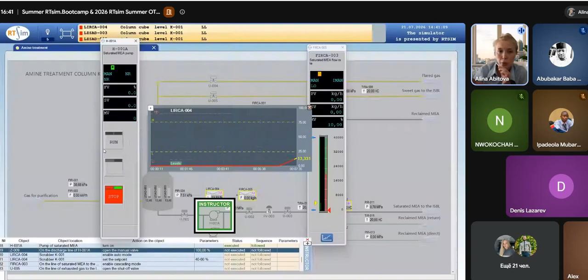Yeah, so right now the level is almost 12%. Right now I guess it will let you open the pump, but it's still critically low, and technologically it will be more correct and most careful for the equipment to turn on the pump when the level is at least like 20-25%. The best way is to wait till it will be in its middle value, so at least 50%.